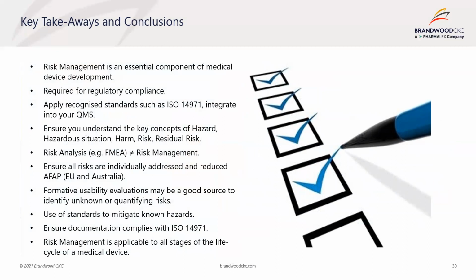Risk analysis, for example, FMEA does not equal risk management. It is important to understand that distinction. Ensure all risks are individually addressed and reduced as far as possible for Europe and Australia. Formative usability evaluations may be a good source to identify unknown or quantifying risks. Use of standards to mitigate known hazards. Ensure documentation complies with ISO 14971. And finally, risk management is applicable to all stages of the life cycle of a medical device.